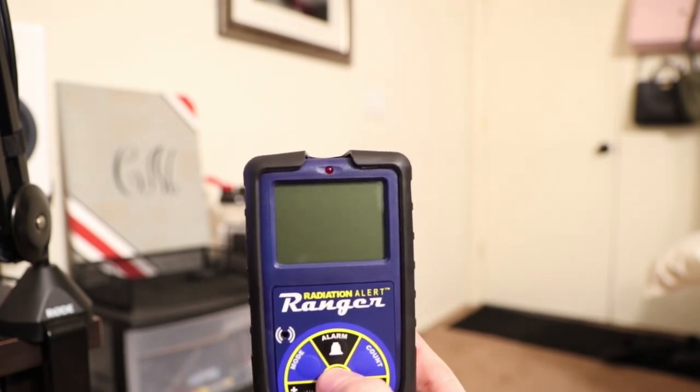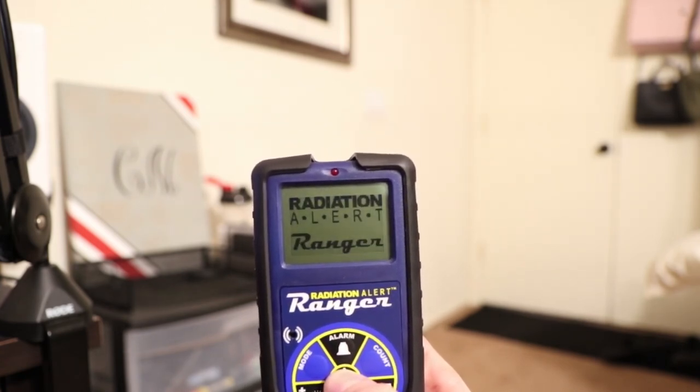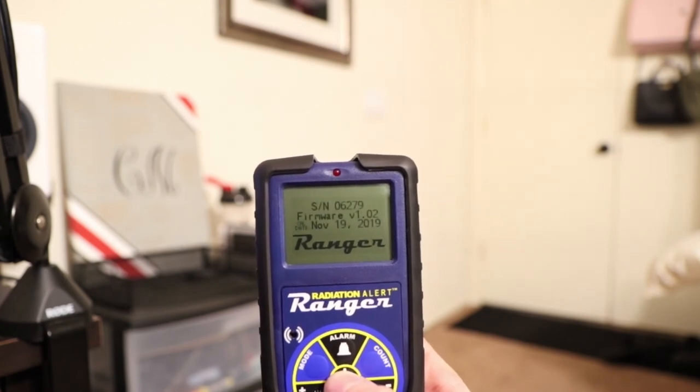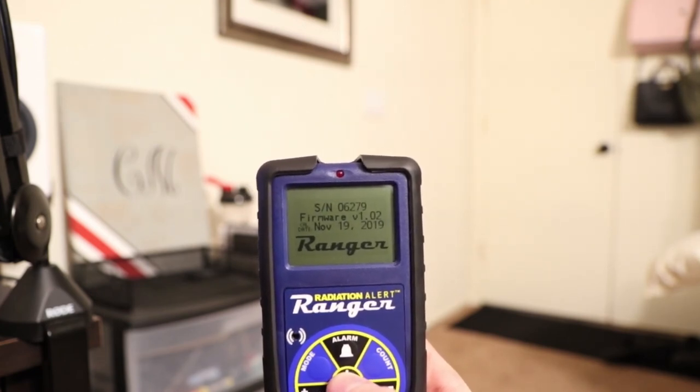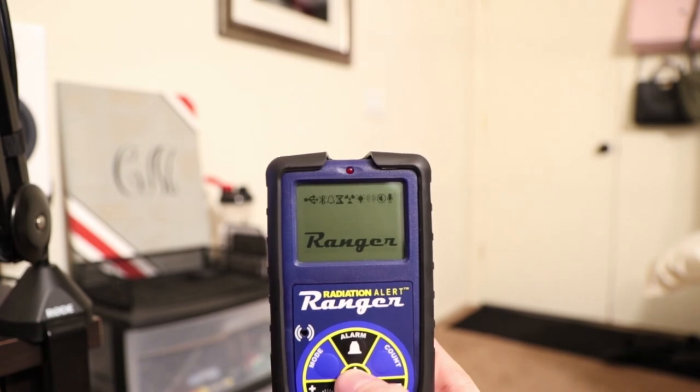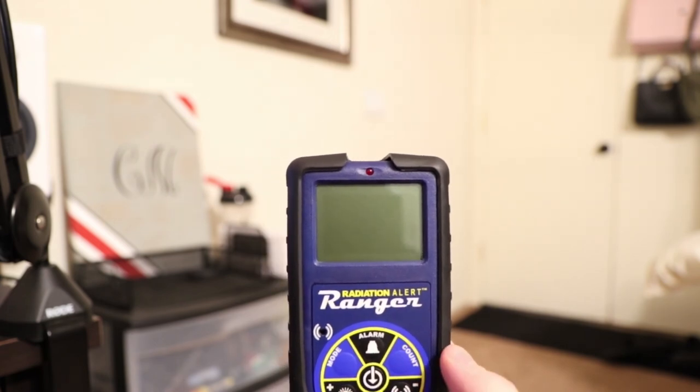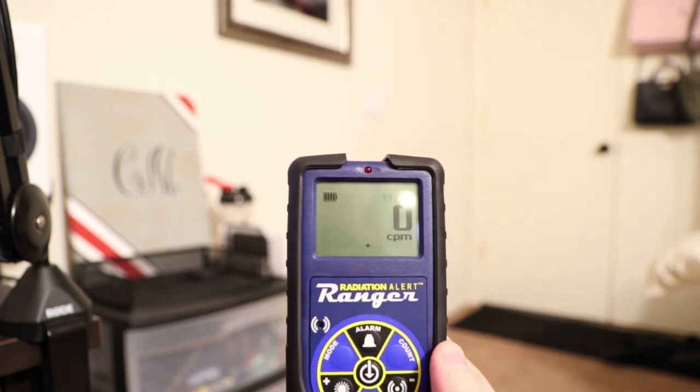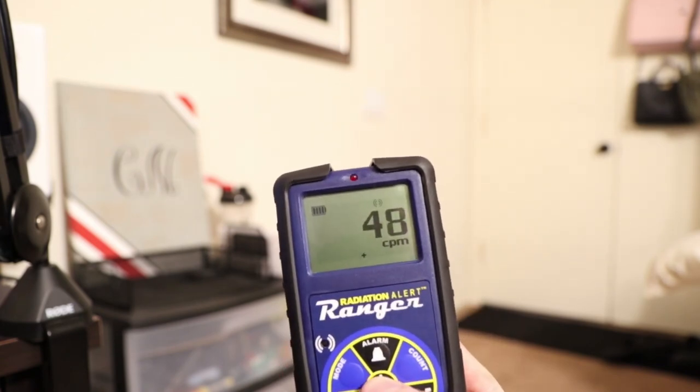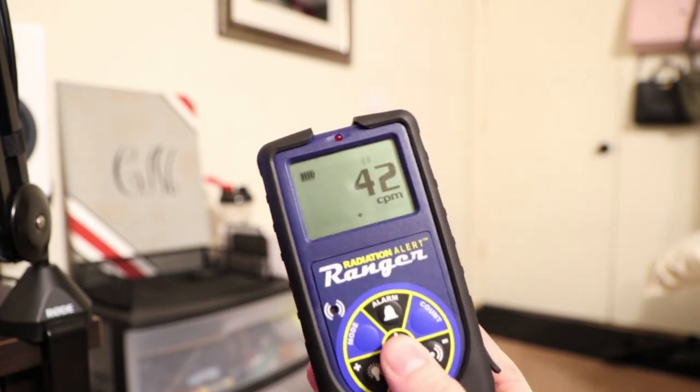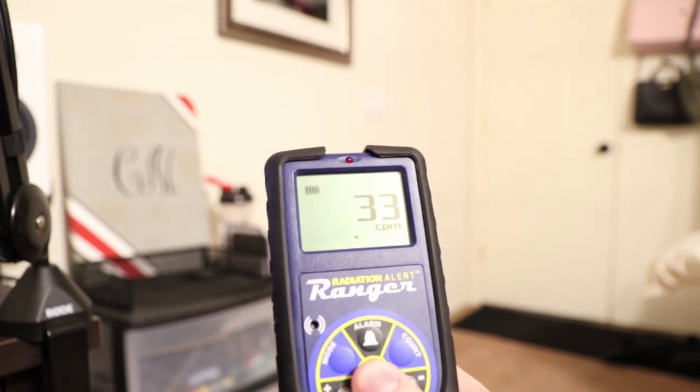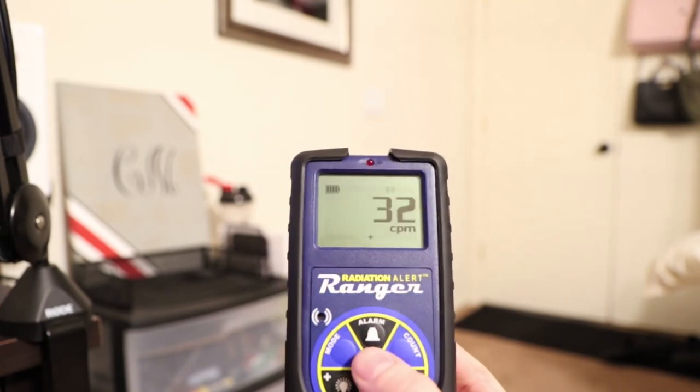Not a whole lot. Press and hold, see radiation alert Ranger. You can see the firmware and the calibration date has changed on it. Not the firmware but just the calibration date because it just got calibrated. Then it's going to do a self test and in about 30 seconds it will beep and it will be ready to use.